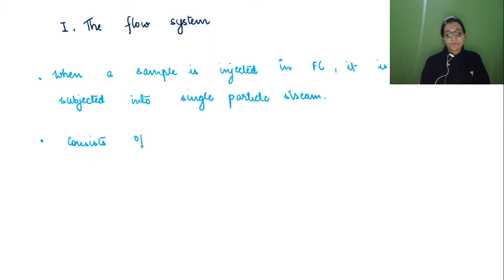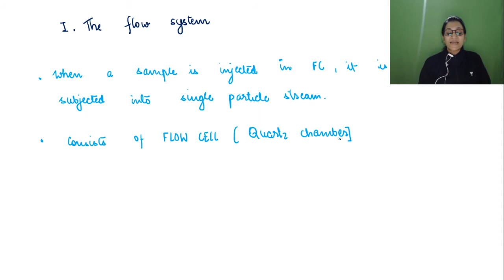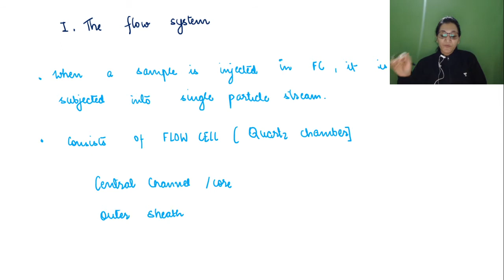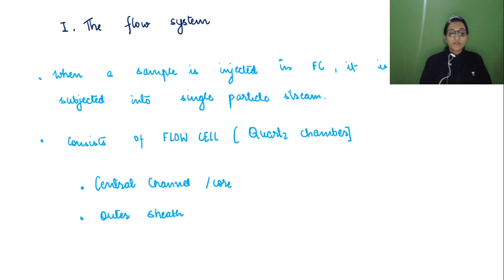The fluidic system consists of a flow cell, which is made up of a quartz chamber. There are two things: a central channel or core and the outer sheath. The central channel is the place from where the sample is injected. The outer sheath contains faster fluid, the sheath fluid, usually 0.9% saline or a suitable buffer, enclosing the central core.